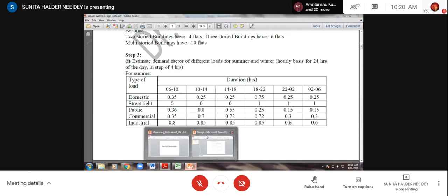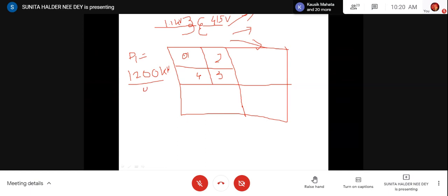So whatever you have drawn, now in any block, we have found connected load, say 1200 kilowatt, in one subblock, say D1. This is the connected load that you have calculated right now. This is not the maximum demand. Say maximum demand is maybe 900, I am assuming. So there will be a variation, a load curve like this somewhere. I do not know how it will be. What the load curve will be depends on the demand factor. Now demand factor we can take from statistical data, or you may assume. Here I am assuming because statistical data we cannot get in this case. But in a practical system we must assume the demand factor from the statistical data available.